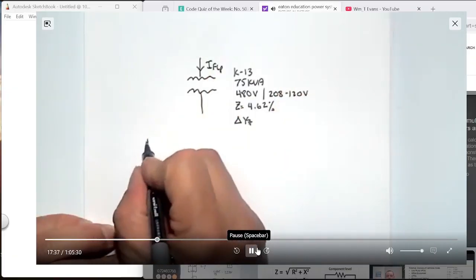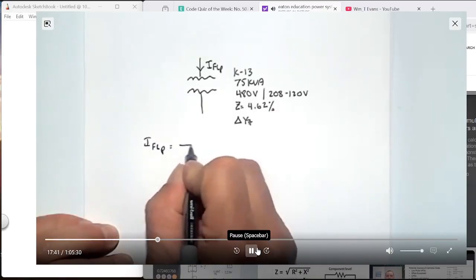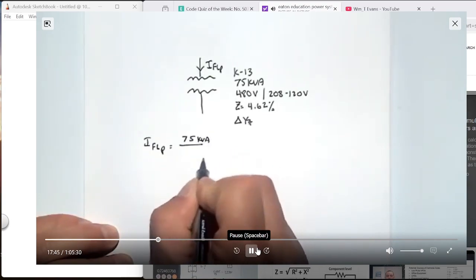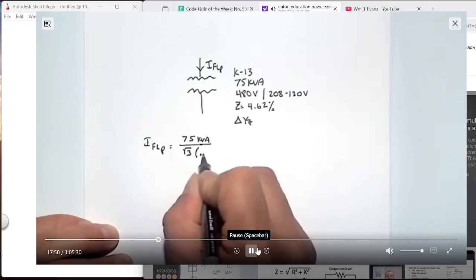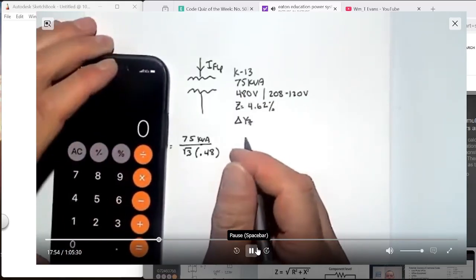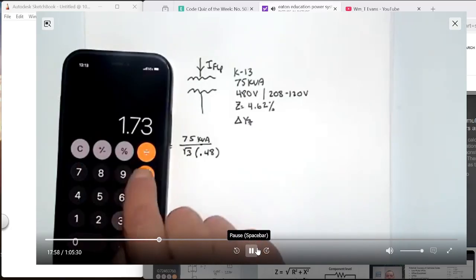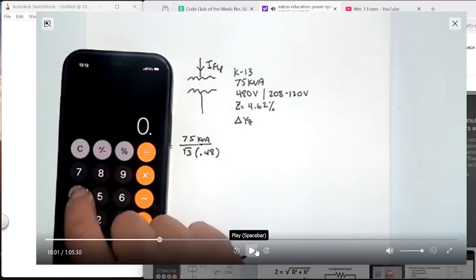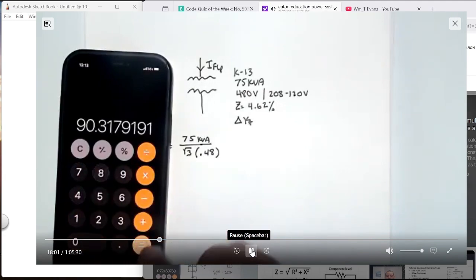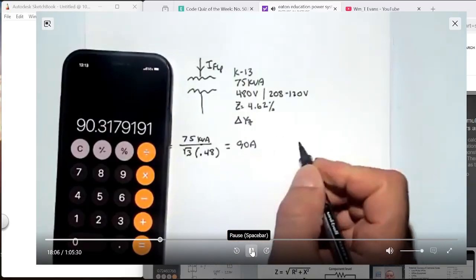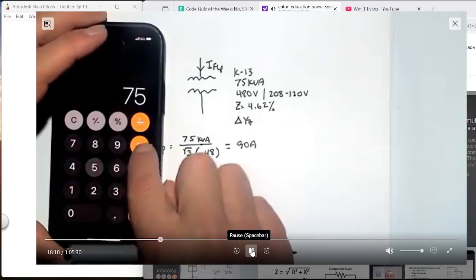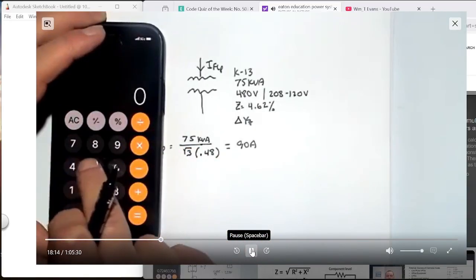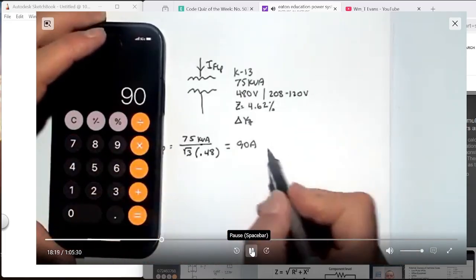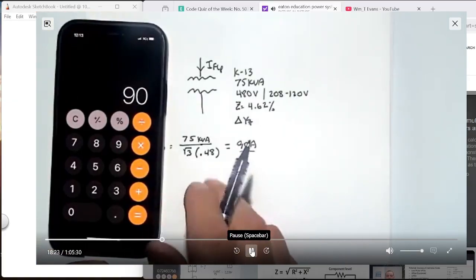All right, so we go back to our equation we had before. I full load primary, in this case again 75 kVA, is kVA divided by the square root of 3 divided by kV. Again, we have to make sure we use 0.48 here. So we take 75 divided by 1.73 divided by 0.48, and we get 90 amps. Remember what I told you earlier? 75 times 1.2 is 90 amps, which is that 1.2 multiplier when you have a 480 volt system.